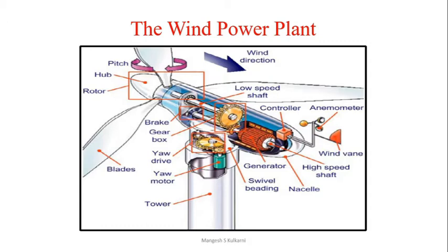When the wind speed is high enough to overcome friction in the wind turbine drivetrain, the controls allow the rotor to rotate, thus producing a very small amount of power. This cut-in wind speed is usually a gentle breeze of about 4 meters per second. Power output increases rapidly as the wind speed increases.